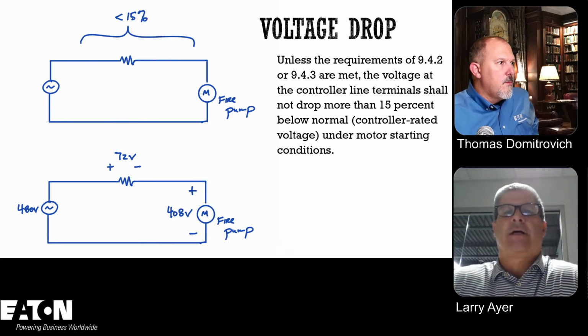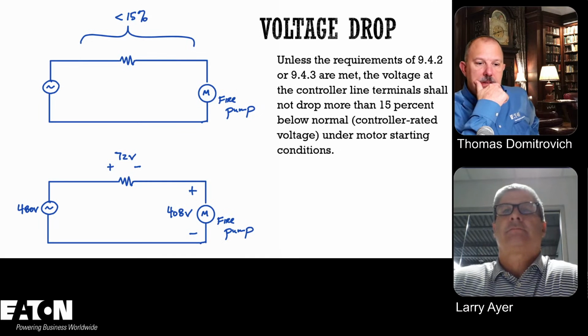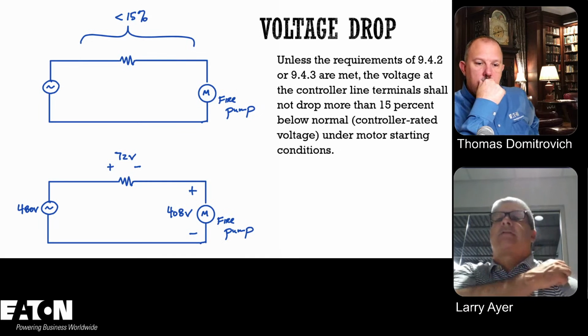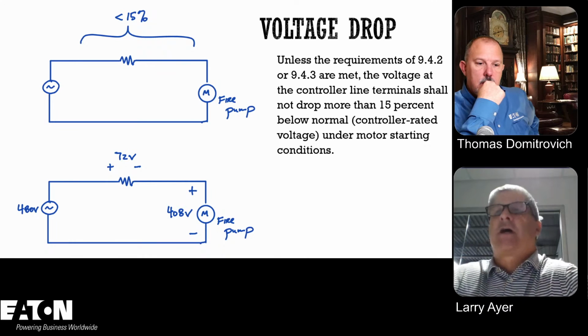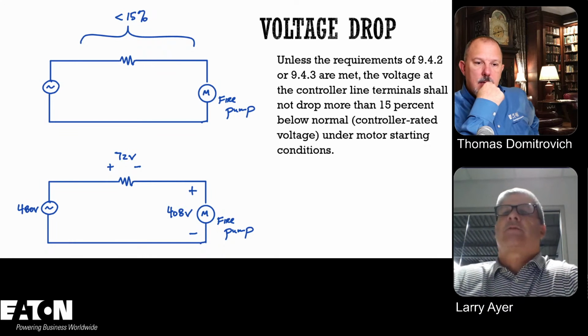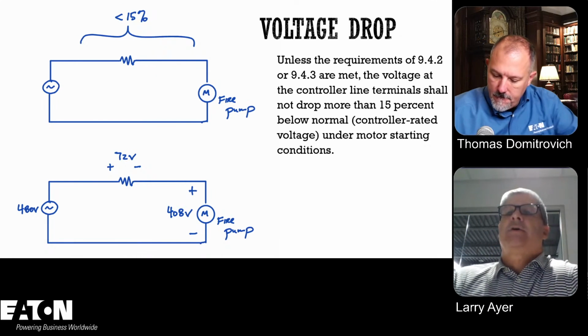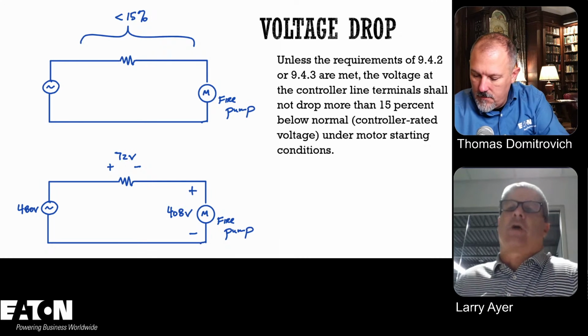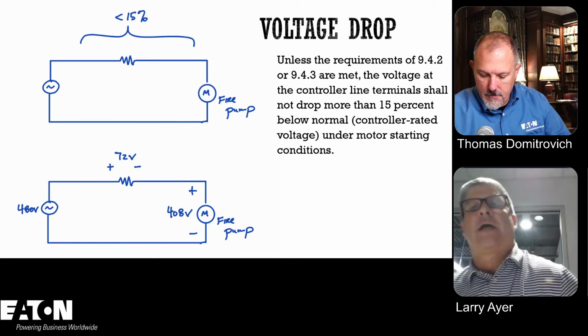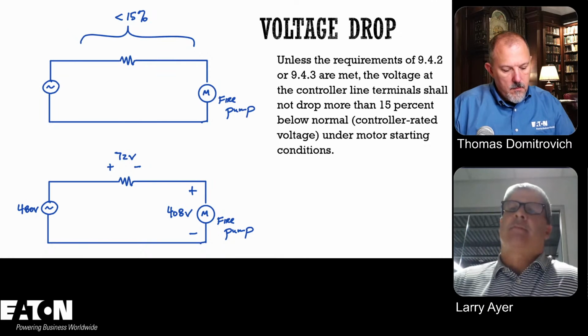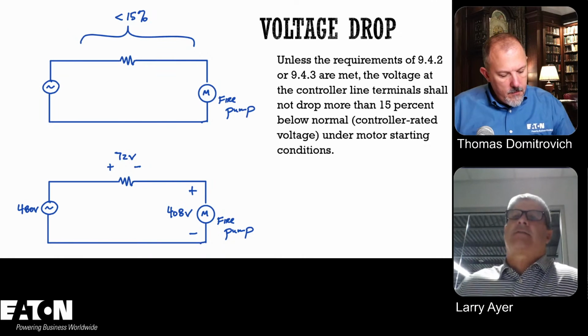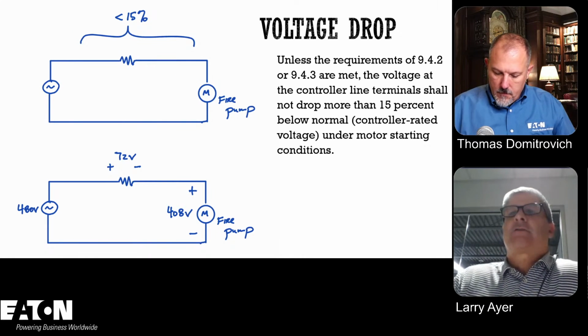So if you want to go to the next slide. So here is kind of an example of a 15% drop for when you start up. So for instance, if you have a 480 volt system, you're allowed to have 72 volt drop. So down to 408 before to allow that motor to start up. So that's 15%.